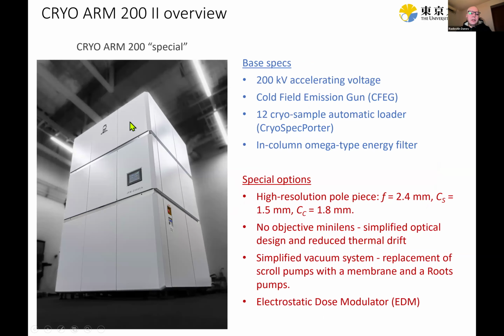Now, the machine we used for these tests is a JEOL CryoARM 200, which is now version 2. At the time we ordered it 3 years ago, it didn't have such a designation, so it was just a 200 kV cryo-EM, which we called special because we requested some modifications. The base specs are 200 kilovolts, cold field emission gun. JEOL's machines are all with the cold field emission gun. It has a 12 sample autoloader and an in-column omega type energy filter. So the JEOL machines have an energy filter as standard.